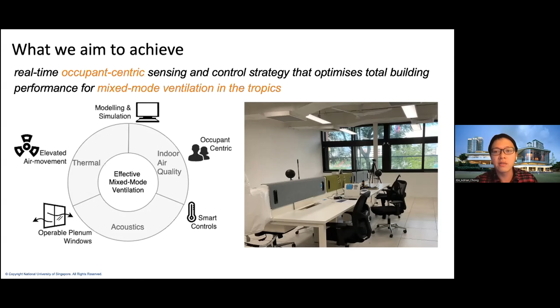How we aim to do this is not to suddenly switch to natural ventilation, but rather we might operate in air conditioning, and if we see that outdoor conditions are going to be good, we move to a concurrent operation—operating the air conditioning system while having the windows slowly open up as we increase the thermal load into the space.